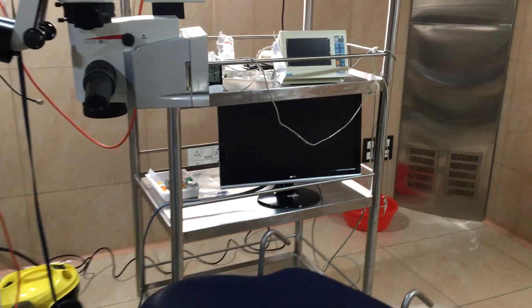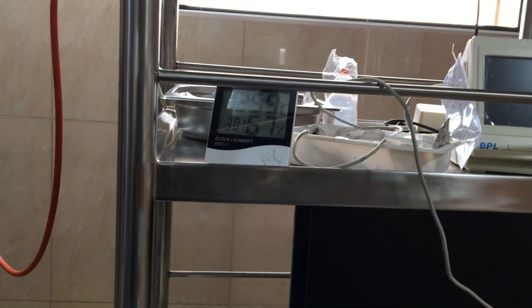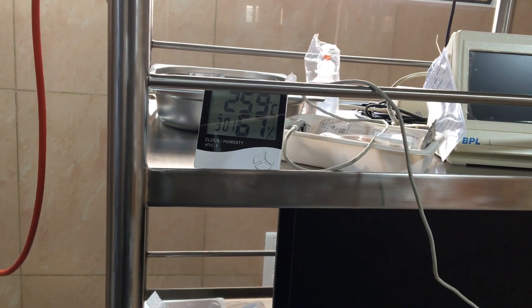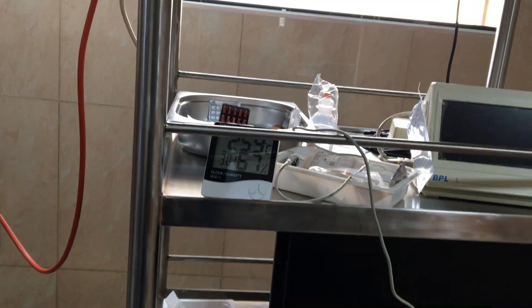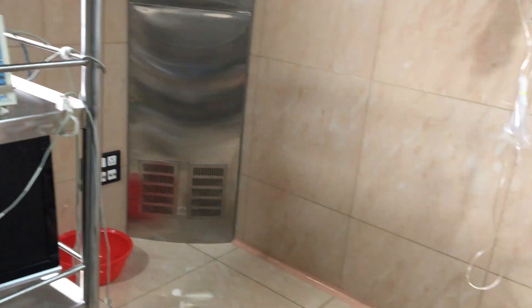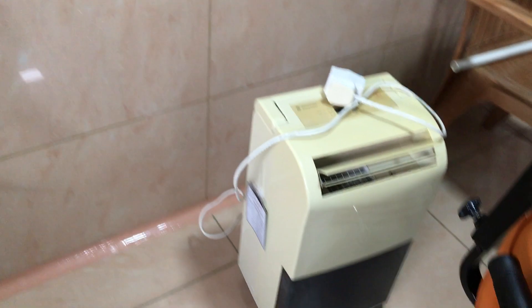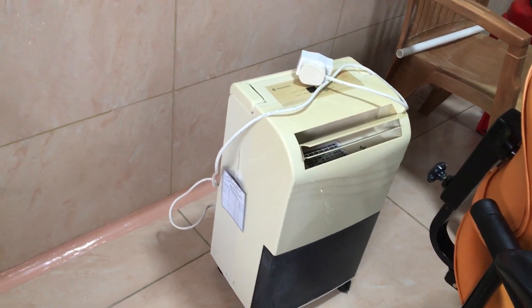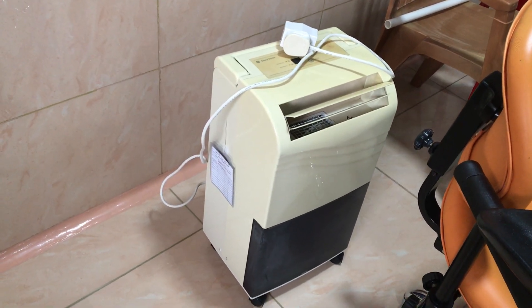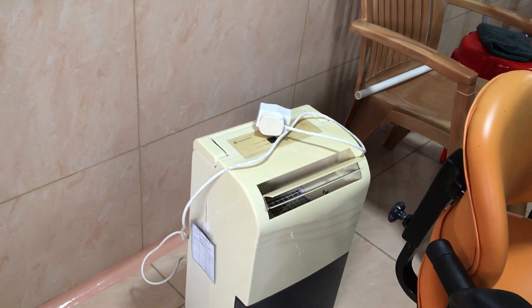There are many small monitors here. Now we have switched off the air conditioner and the temperature has gone up to 25.9°C and the humidity is 67%. We keep the humidity around 40 to 50% all the time by two methods. As long as the air conditioner is on, the AC will maintain it. When the AC is switched off, we use a gadget called a dehumidifier. We switch off the dehumidifier at end of day and staff switch it on again in the morning. Humidity does go up at night, generally to the 60s and 65s, which suffices for us.